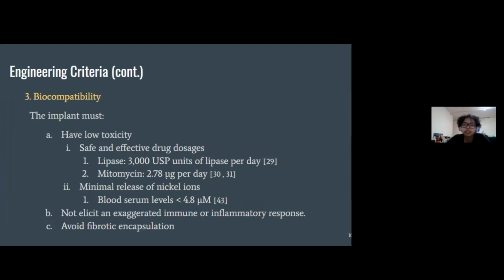The device must also release minimal nickel ions from the nitinol core, so as to never exceed the toxic blood serum level of greater than 4.8 micromolar. To be effective, the device also cannot instigate a detrimental immune or inflammatory response and must avoid fibrotic encapsulation.